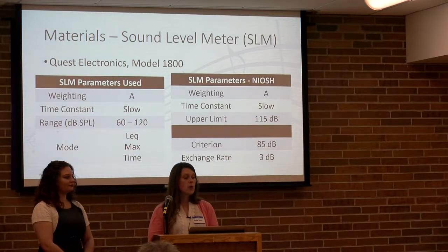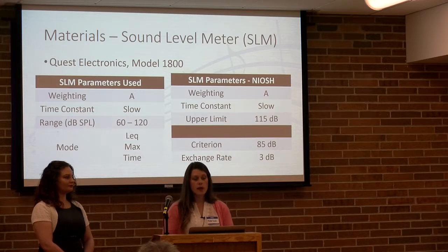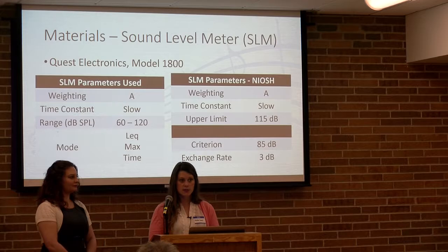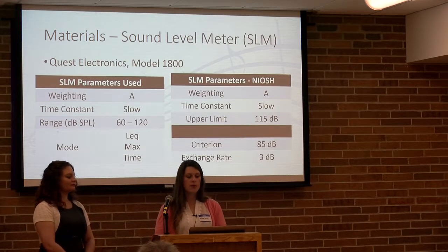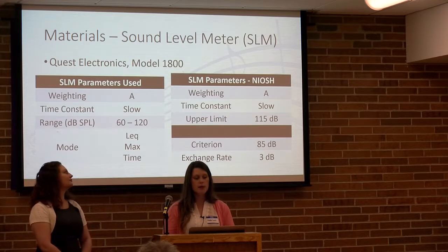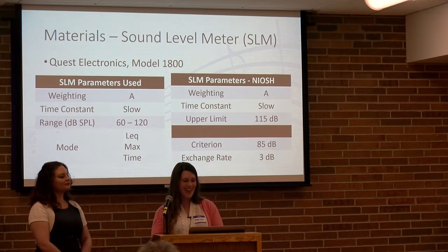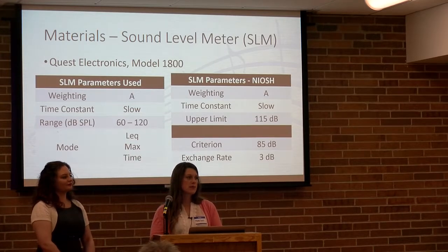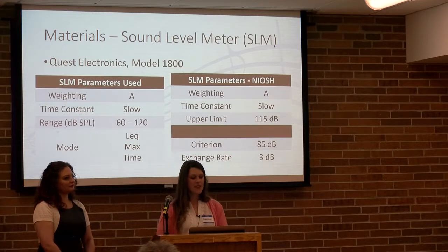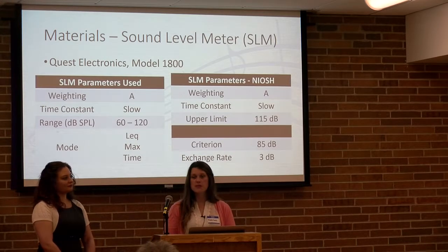I used a level 1 Quest Electronics Model 1800 sound level meter. The sound level meter was calibrated to the manufacturer's specifications and met the American National Standards Institute specifications. If you look to the right, you can see the parameters required for NIOSH comparisons. And the table on the left is the parameters I used in my study. A weighting is used because this is the frequency response that best resembles that of a human ear. The time constant of slow was used because this allows the sound level meter to respond to fluctuations occurring within 1 second.